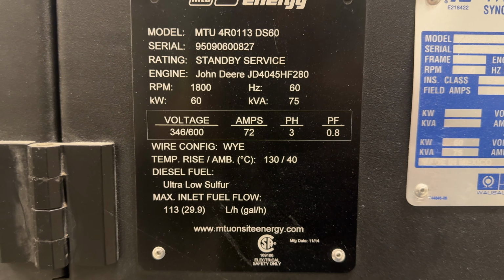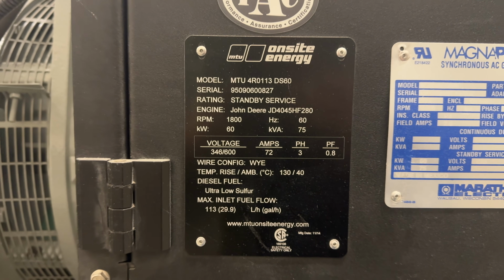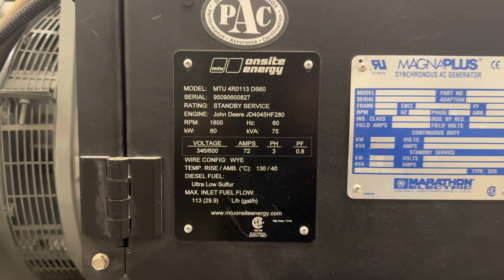Ignore that it says 346. That should say 347/600. This is a 3-phase generator, of course. 72 amps, of course, is a quite small portion of this building's total 1200 amp service at 600 volt, but that's because this is only doing emergency load. It's not running any heat, any cooling. It's not doing the elevator in this building like they do in many. It's just doing emergency lighting, and that smoke control system is a huge load.